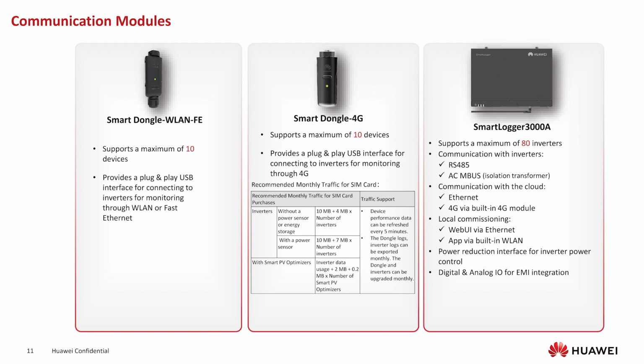Then if there's no internet, you can go for the Smart Dongle 4G. You can put a SIM card in there, and then you can communicate with the internet via that. And then we have the Smart Logger 3000, which supports up to 80 devices. We recommend this for any projects over 1 megawatt or more than 10 inverters, okay?